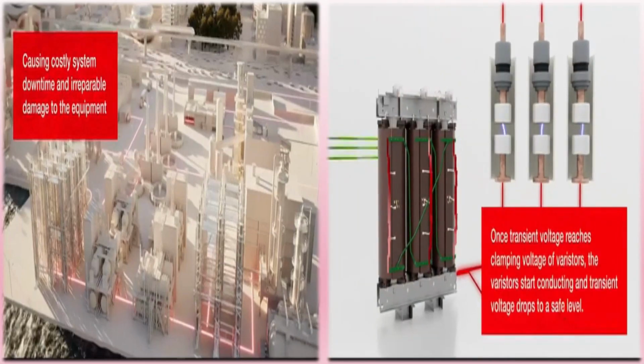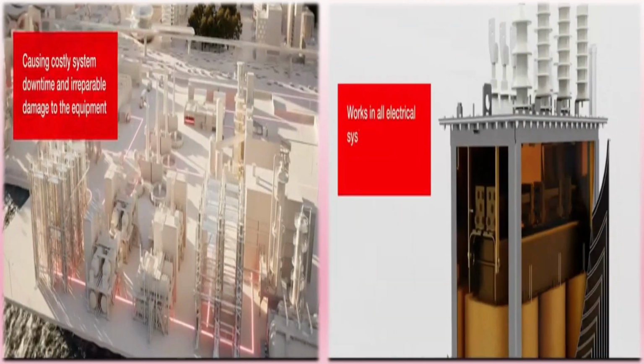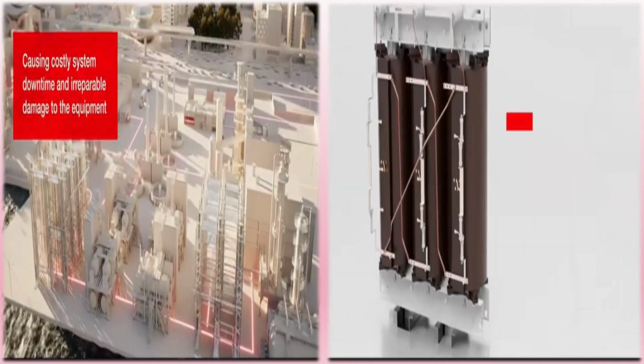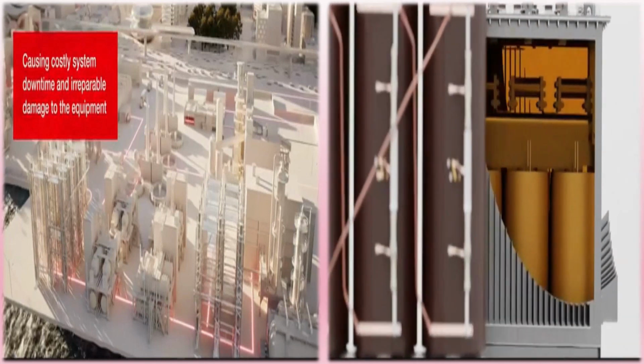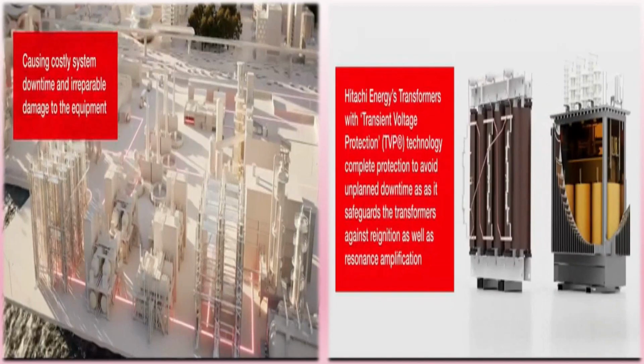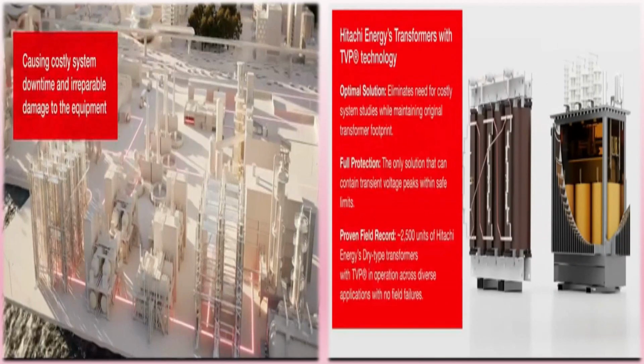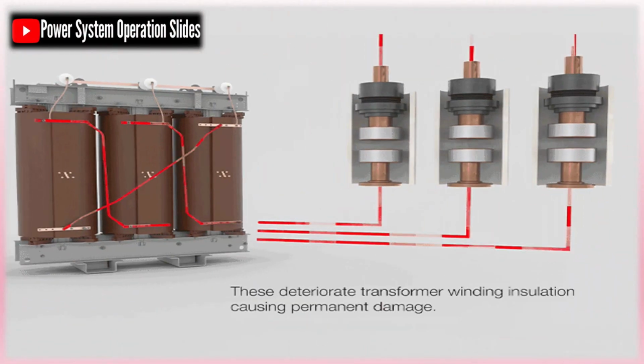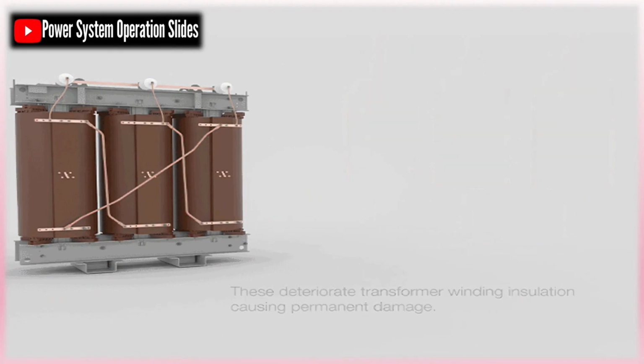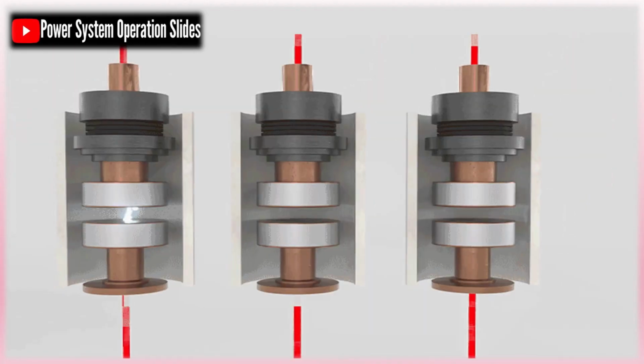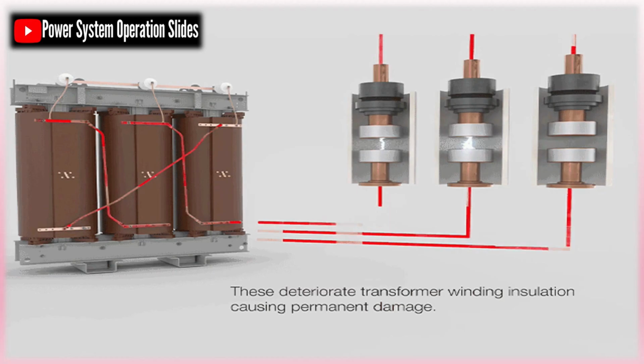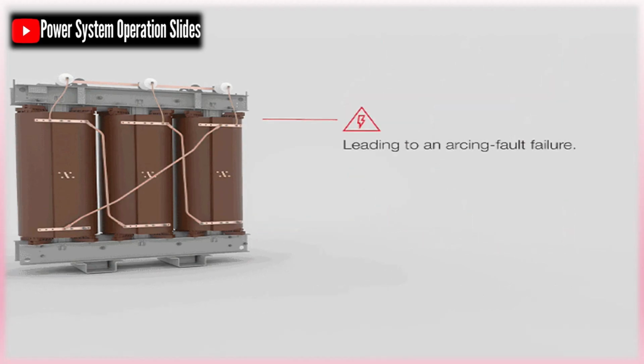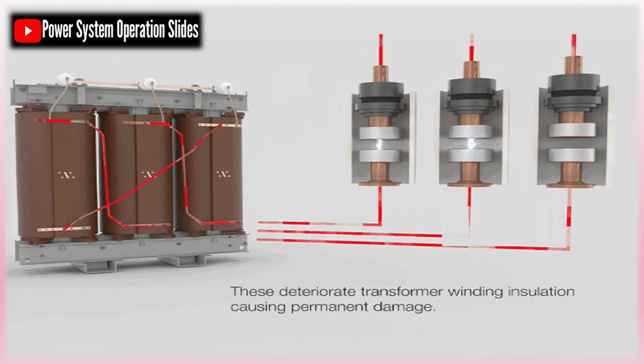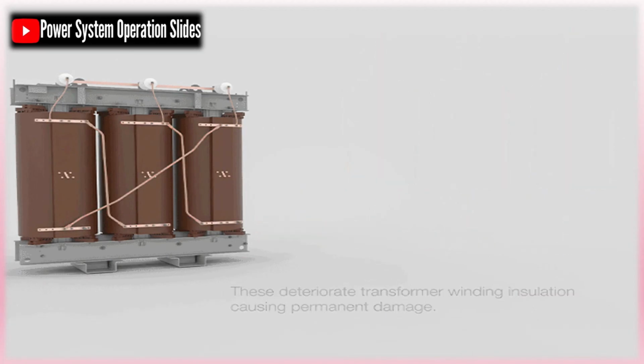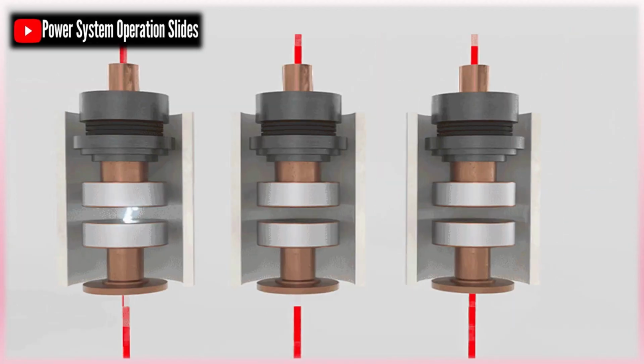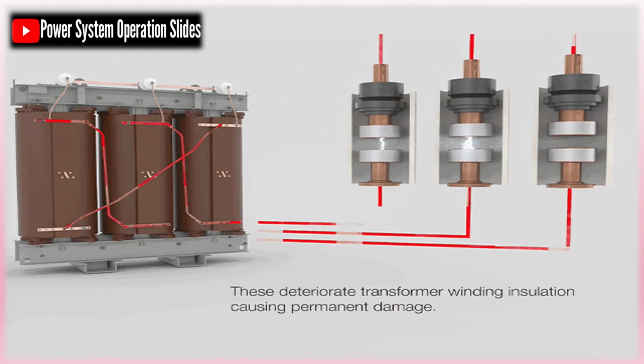To address this challenge, Hitachi Energy has developed an innovative solution known as transient voltage protection. Transient voltage protection is a patented, integrated protection system designed to mitigate fast transient overvoltages directly within the transformer. Unlike conventional external protection devices such as surge arresters or RC snubber circuits, TVP is embedded inside the transformer windings during manufacturing.